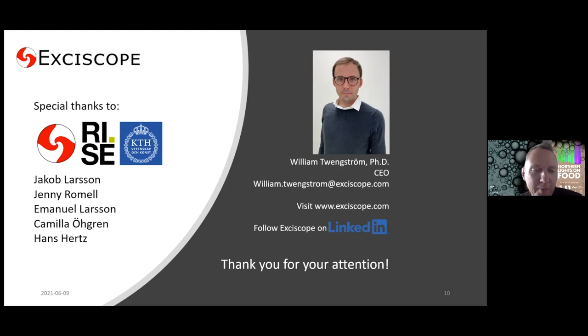Question: What about the maintenance of the liquid jet source — people say it requires some effort? It does require more effort than a solid anode tube. You have to change cathodes and nozzles every now and then, but typically it can run for several months without maintenance, so it's pretty manageable. Another question: could you comment on the available incident energy range? Acceleration voltages are up to 160 kilovolts. The emission lines of the gallium, indium, and tin in the alloy are at around 10 keV and around 25 keV, so the efficient x-ray energies are around 10 up to 30 keV.